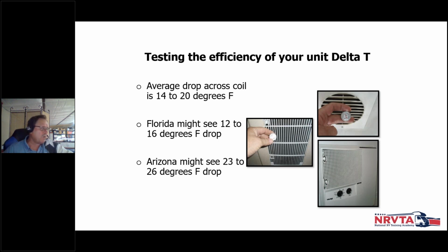So you might be in Florida seeing a lot of high humidity, and you may see a 12 to 16 degree delta instead of the 14 to 20. Some of the work is being expended in getting rid of the water. Now, let's say you go to some place where there's desert air and not a lot of humidity. You might see a higher delta, but by golly, it might be 115 degrees out there. So keep in mind that where you are is going to make a difference in what kind of delta you're going to see out of that air conditioner.